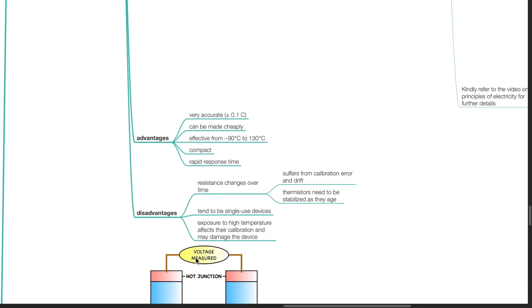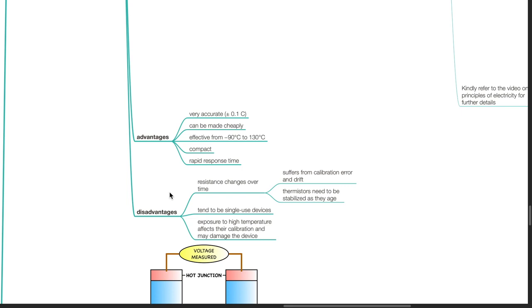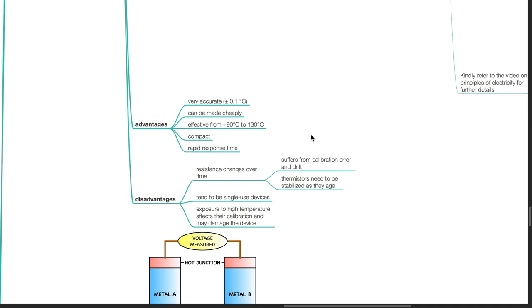Advantages of the thermistor: it is very accurate to plus or minus 0.1 degree Celsius. It can be made cheaply. It is effective from negative 90 to 130 degrees Celsius. It is compact and has a rapid response time. Disadvantages: the resistance changes over time. It suffers from calibration error and drift. Thermistors need to be stabilized as they age, tend to be single-use devices, and exposure to high temperature affects their calibration and may damage the device.